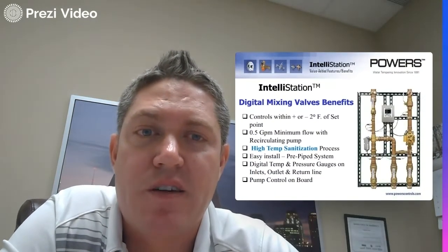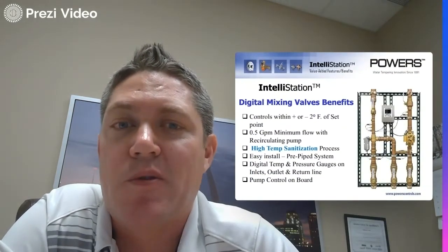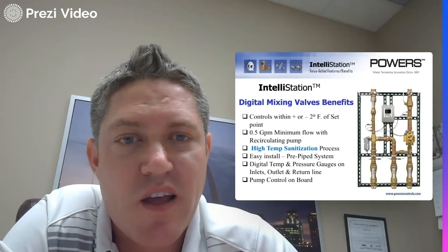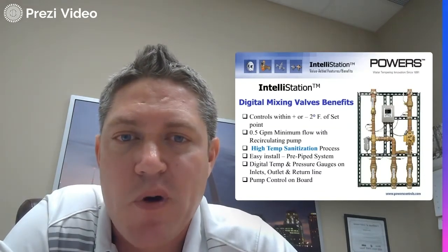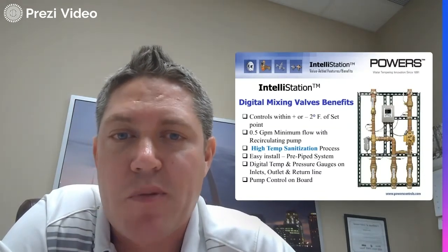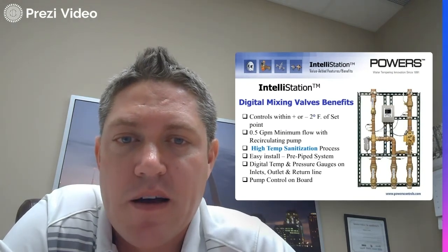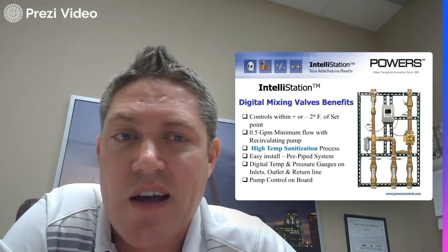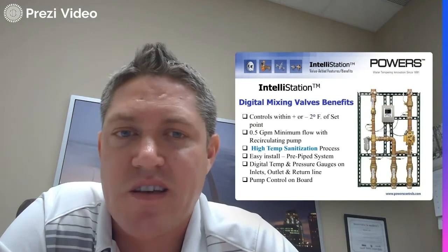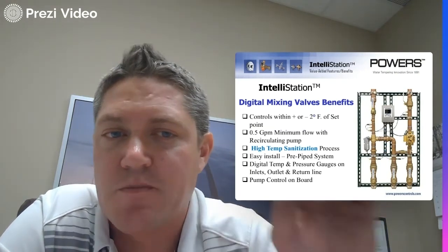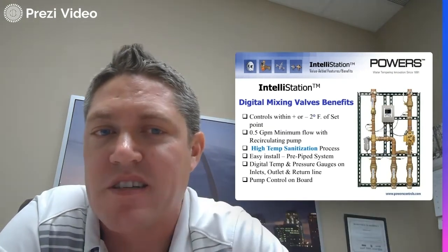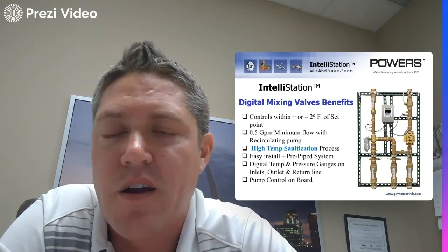Okay, let's move on with the digital mixing valves. The first digital mixing valve Powers came out with was the Intellistation. So like we said, plus or minus 2 degrees from set point, 0.5 gallon per minute minimum flow rate, and a high temp sanitization process. It's easy to do a sanitization on a digital mixing valve. You just jump into your programming. That's a touch screen on the controller there.